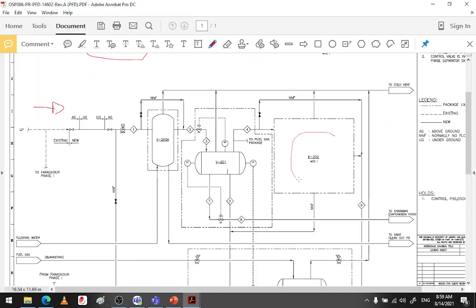Because in the basis of design, as you will receive today, or if you already downloaded the drive, you will see the composition we are receiving from our reservoir engineering, saying that we have a gas quantity, a water quantity, a condensate quantity, and then almost 20 kilograms of sand per day. Based on that, this 20 kilograms of sand per day, we need to remove it from the stream. Why? Because here is the compressor.